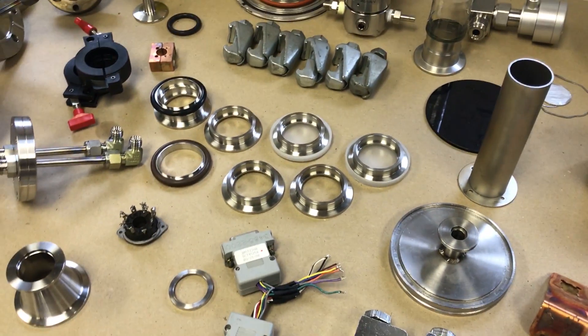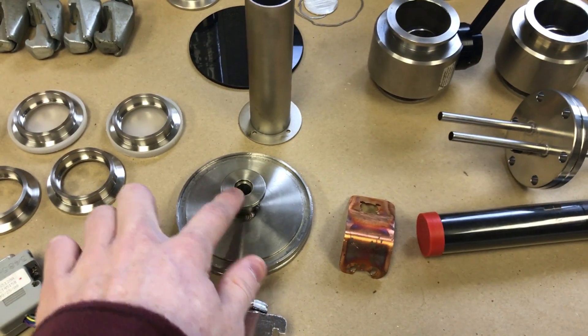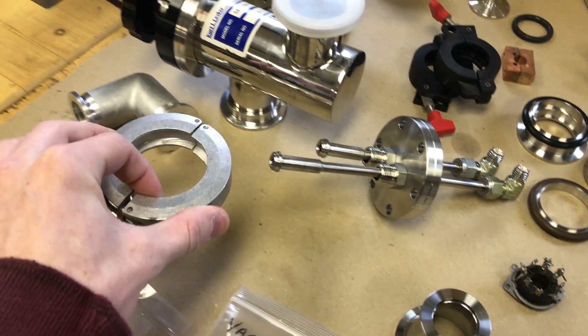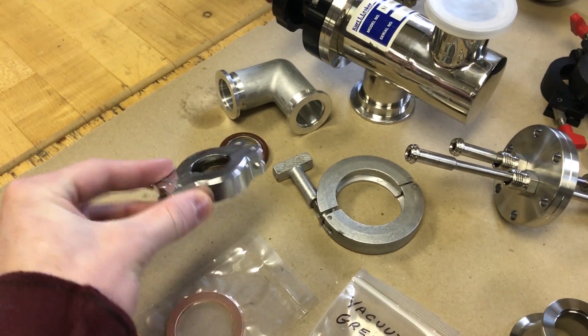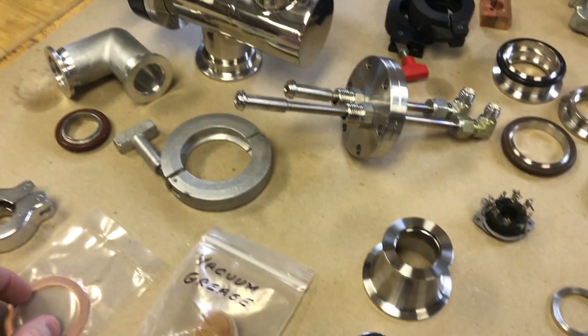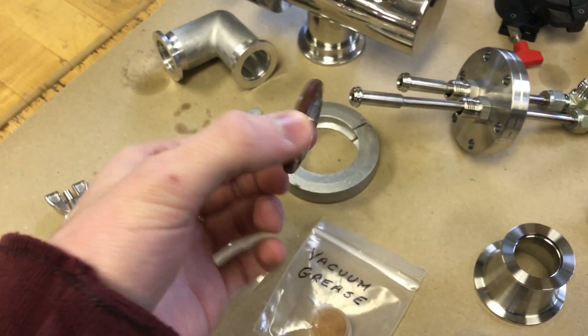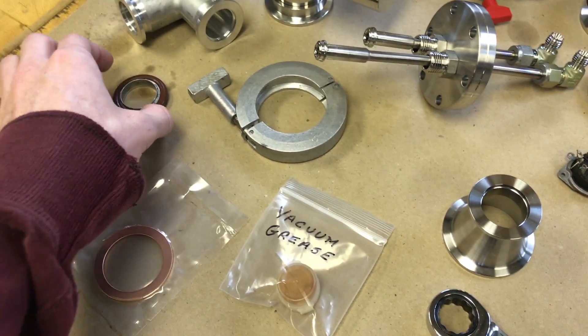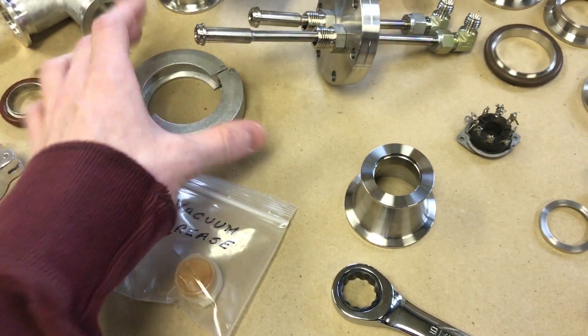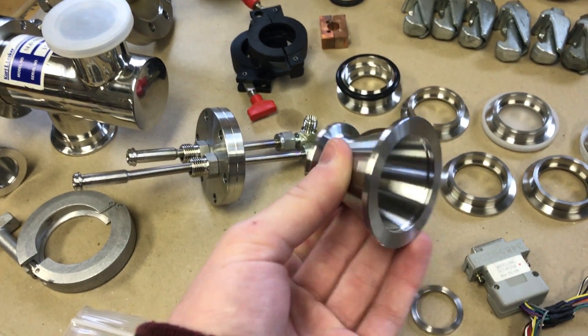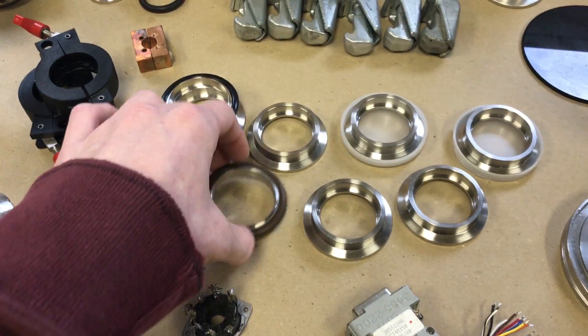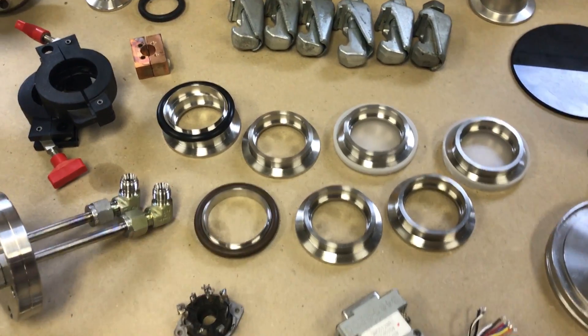So this is a KF-40 right here. There's a few common sizes you'll see are KF-10, KF-16, KF-25, and KF-40. So this uses a clamp like this. This is a KF-40 clamp. This is a KF-16 clamp. And then the centering rings look like this. And the clamp goes around the connector.